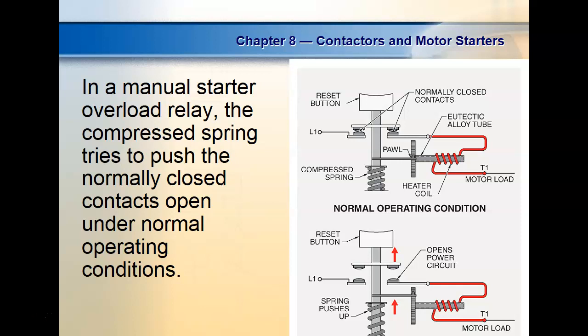So we have to put the right size in. You'll see overload contacts that are designed to run at your voltage. So you have to put an overload heater in there that produces the same heat at a lower voltage, right? You have to put one that creates the same heat at a higher voltage. The problem you have is the electrician or somebody has to change that. So they might have these overloads in a high voltage circuit and put them in a low voltage one, or in a low voltage circuit they put in a high voltage one, and they're not going to trip.